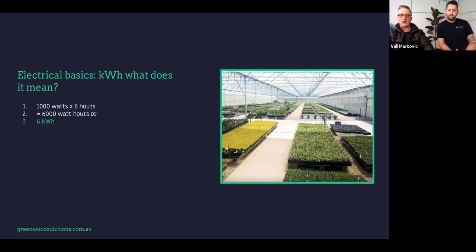You find the ratings of your appliances, whether it's a nursery load specifically or an office load - we'll talk about that difference - and you'll be able to see exactly what a particular pump on average is costing you. Simple maths, but you'd be surprised how many people get this wrong, especially electricians, confusing kilowatts and kilowatt hours. For instance, that 1,000 watt or 1 kilowatt pump is the power rating; the energy is how long that is on for. Time and again I have to correct electricians on this as I go around Australia conducting training specifically for commercial solar design, amongst other things. It's a really important thing to get correct.